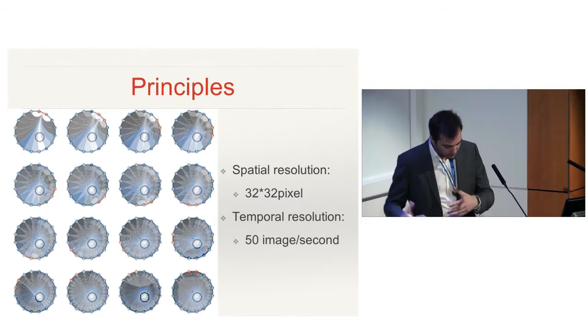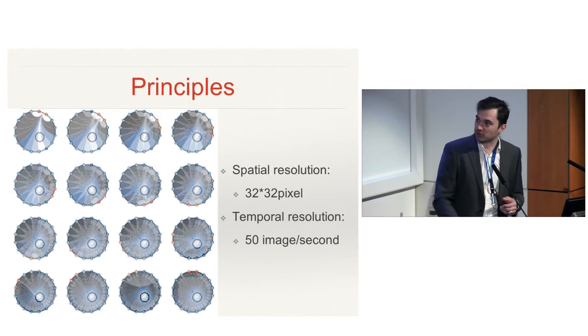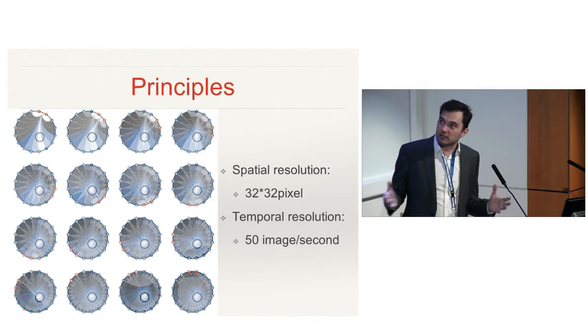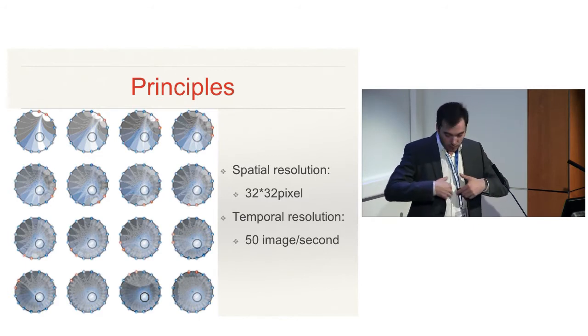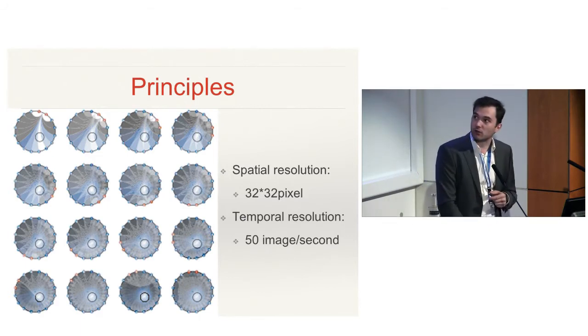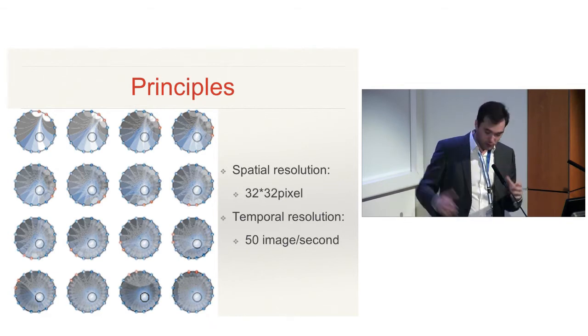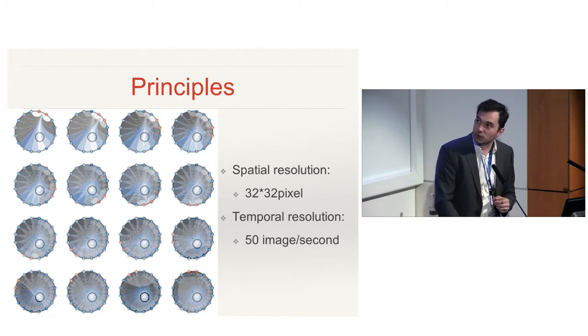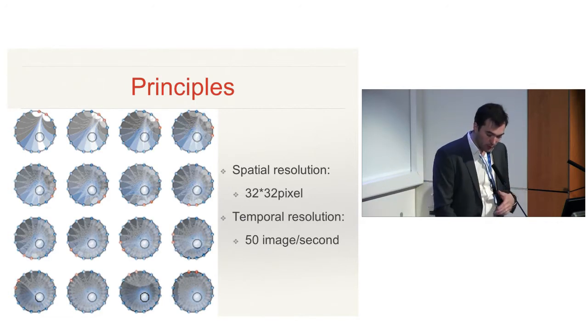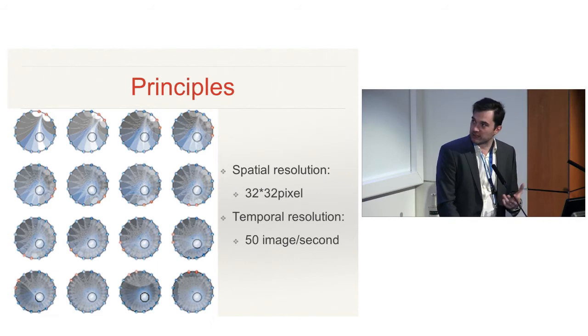To put this into images that make sense, the EIT devices work by using a belt with electrodes — usually 16 electrodes — where a first electrode sends an electrical impulse captured by the other 15 electrodes. By doing that, you draw a map of the diffusion of the electricity around the patient, just like a CT would go around the patient, and you are able to produce a detailed image of what is happening.